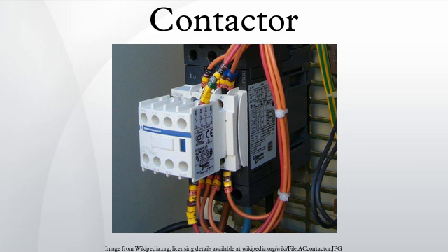Sometimes an economizer circuit is also installed to reduce the power required to keep a contactor closed. An auxiliary contact reduces coil current after the contactor closes. A somewhat greater amount of power is required to initially close a contactor than is required to keep it closed. Such a circuit can save a substantial amount of power and allow the energized coil to stay cooler. Economizer circuits are nearly always applied on direct current contactor coils and on large alternating current contactor coils.